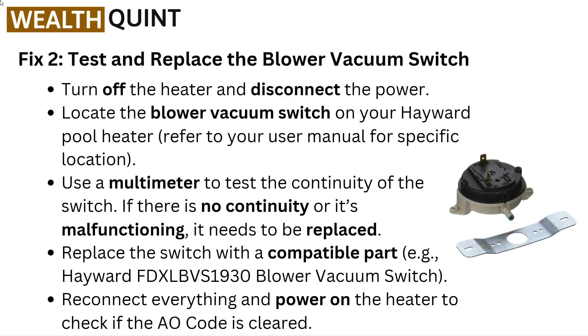Fix 2: test and replace the blower vacuum switch. Turn off the heater and disconnect the power. Locate the blower vacuum switch on your Hayward Pool Heater — refer to your user manual for the specific location. Use a multimeter to test the continuity of the switch. If there is no continuity or it's malfunctioning, replace it with a compatible part such as the Hayward FDXLBVS1930 blower vacuum switch. Reconnect everything and power on the heater to check if the AO code is cleared.